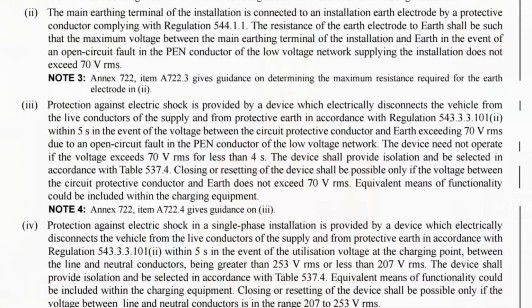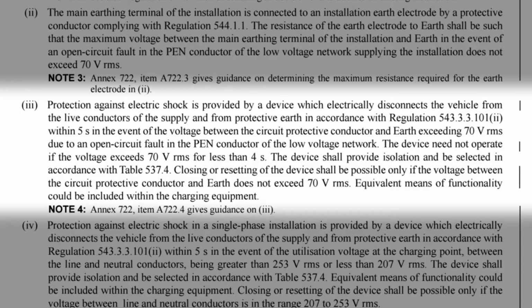Number one, they are not the most common types of situation where you'll be installing an EV charge point, and two, they do not require the use of a reference earth electrode. Now, what is an earth reference electrode, I hear you cry? Well, let's look to the next indent to give us a clue.